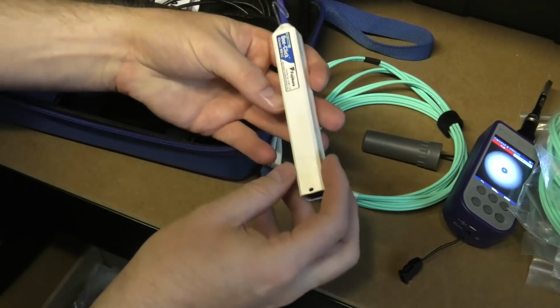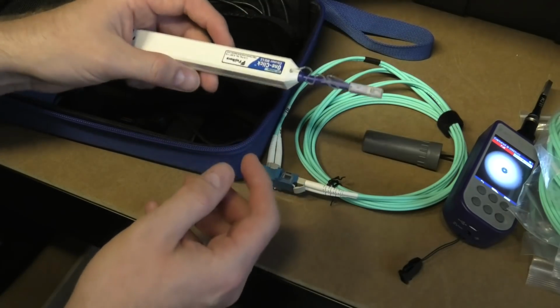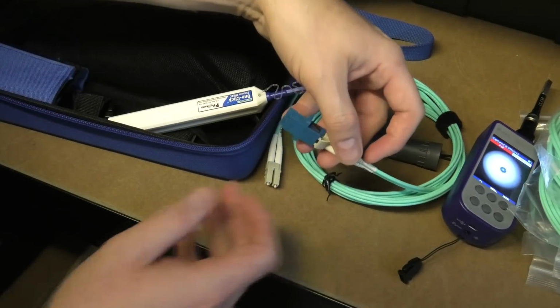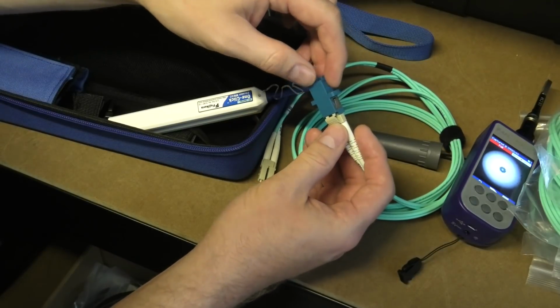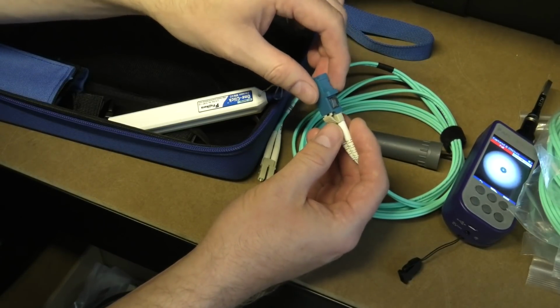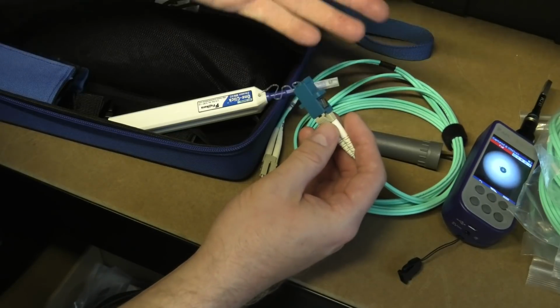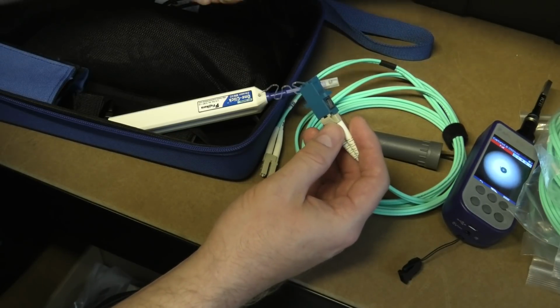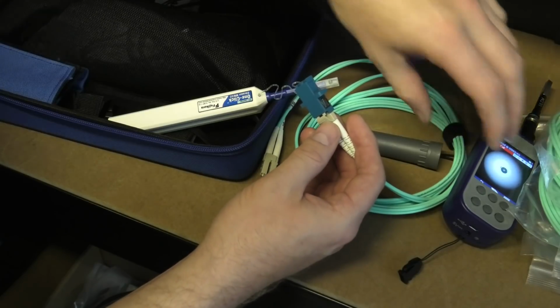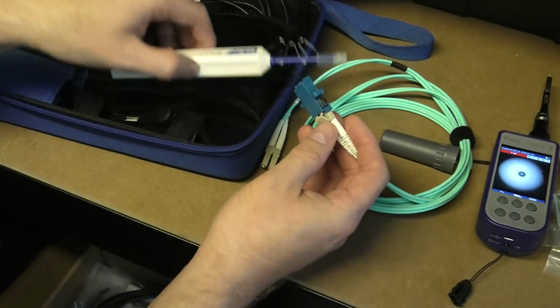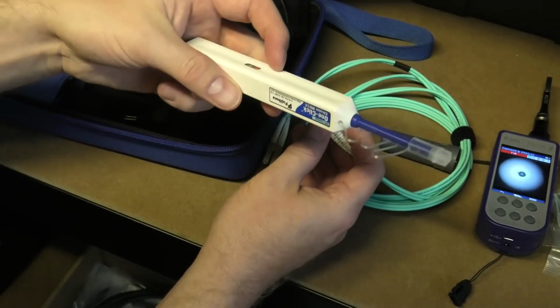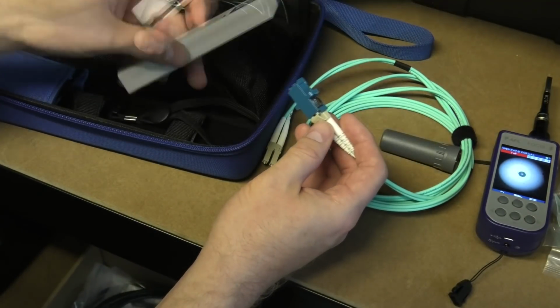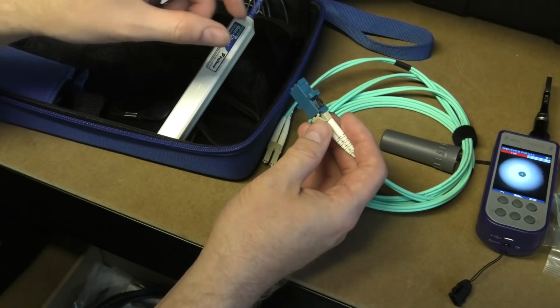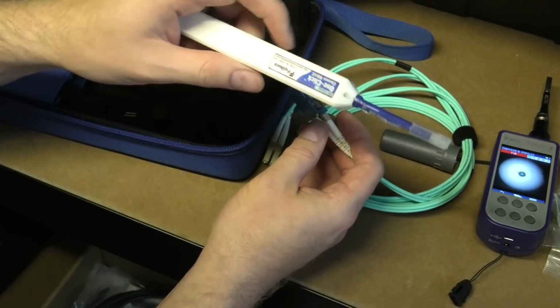Both of these did not survive the test, so we can clean them. For that you often use a cleaning stick like this. If they're really dirty, I've also had luck starting out by just polishing it on a piece of cloth, like a shirt, if it's not too dirty, because these are expensive, and if it's very dirty, removing some of the dirt another way is better than clicking this 50 times.